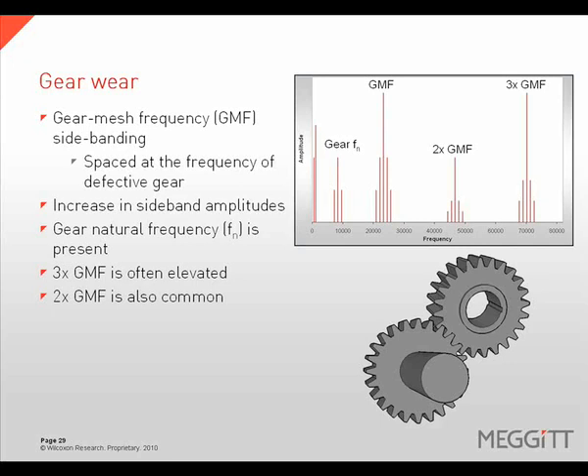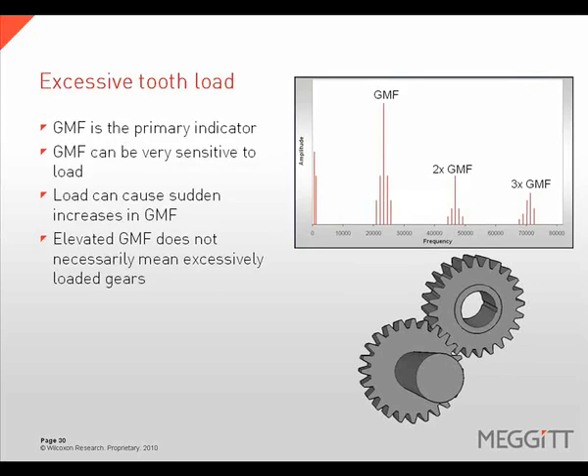Gear wear is characterized by elevated levels of gear mesh frequency and harmonics, with sidebands spaced at running speed of the defective gear. As gear wear progresses, the sideband amplitudes will increase as well as the number of sidebands. The gear natural frequency can be present, and often the 2x and 3x gear mesh frequency amplitudes are elevated. Gear mesh frequency is also the primary indicator of excessively loaded gears, and can be very sensitive to load, causing sudden increases or decreases in amplitude as load changes.